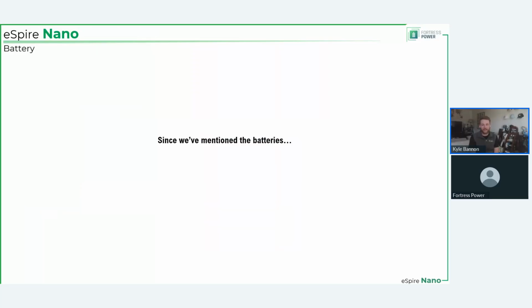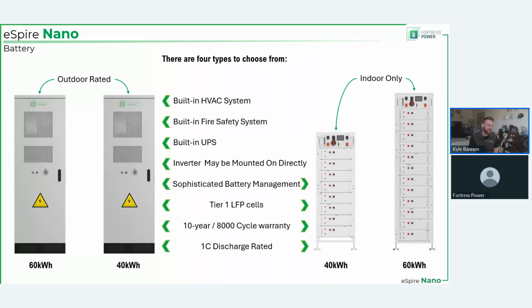We haven't actually talked about the batteries yet, but this screen really breaks down the full system, what you're getting from both an inverter standpoint and a battery standpoint. The cells themselves are all LFP, 10-year warranty, 8,000 cycles. We can discharge up to 1C, which is great. In the past we typically limited our systems to 0.5C, and in general we're still trying to limit these systems to 0.5C, but it can discharge at a full 1C.